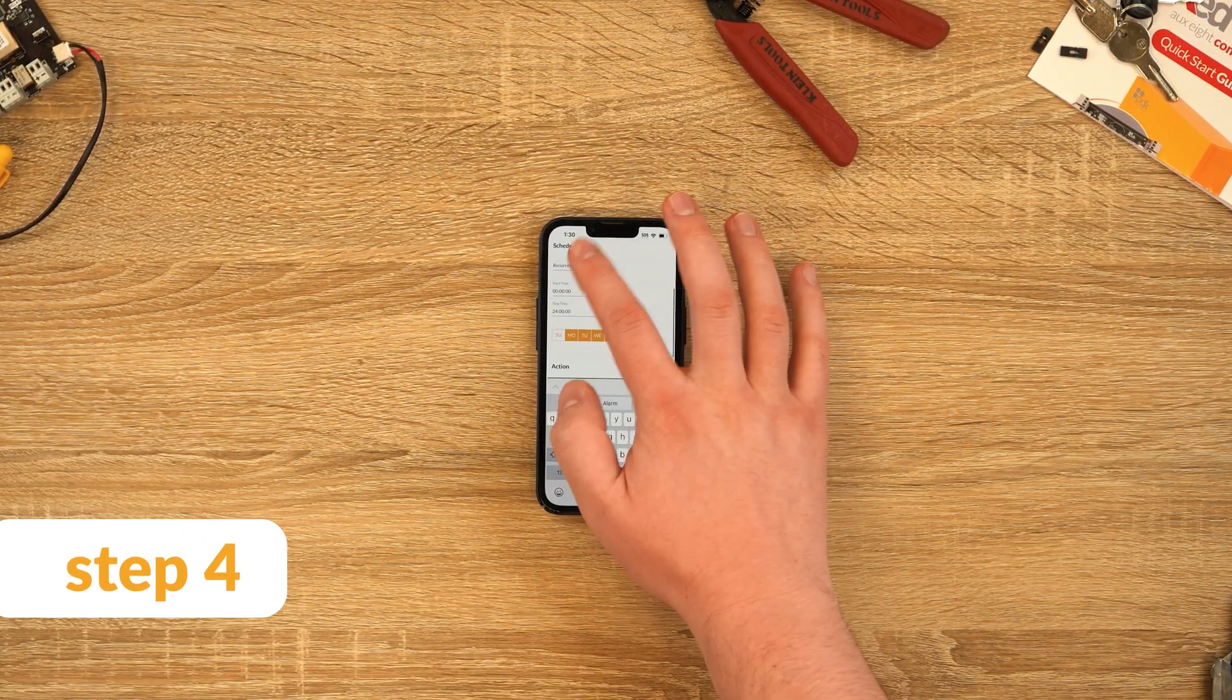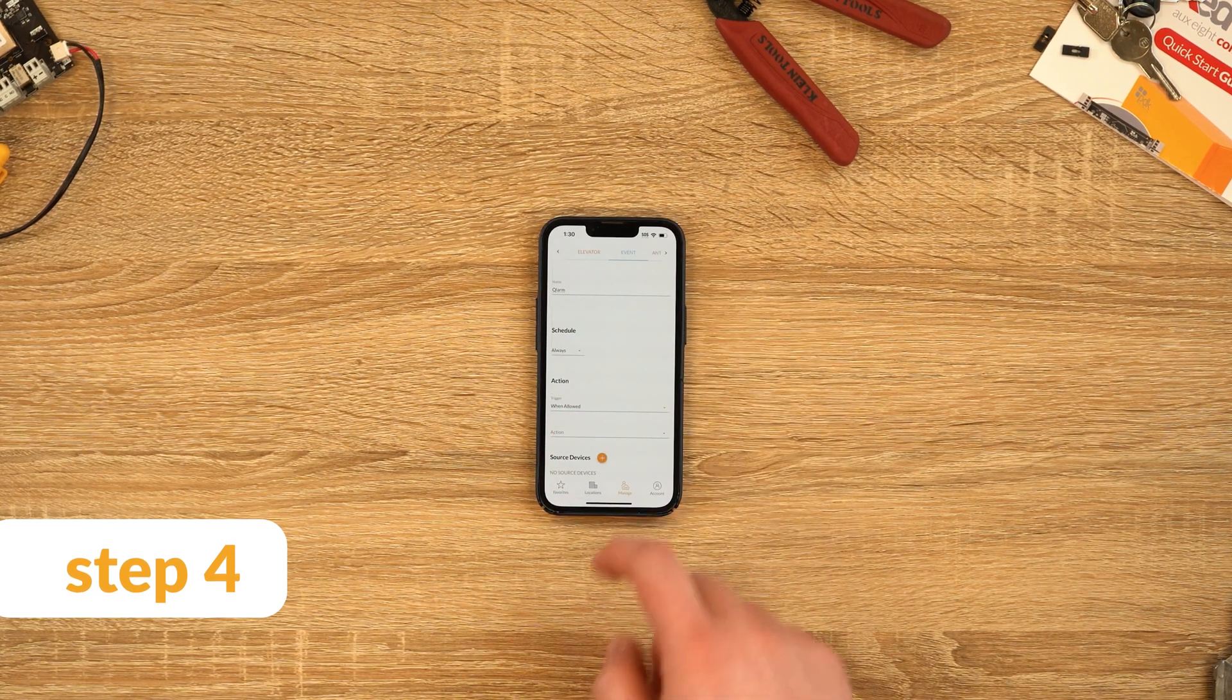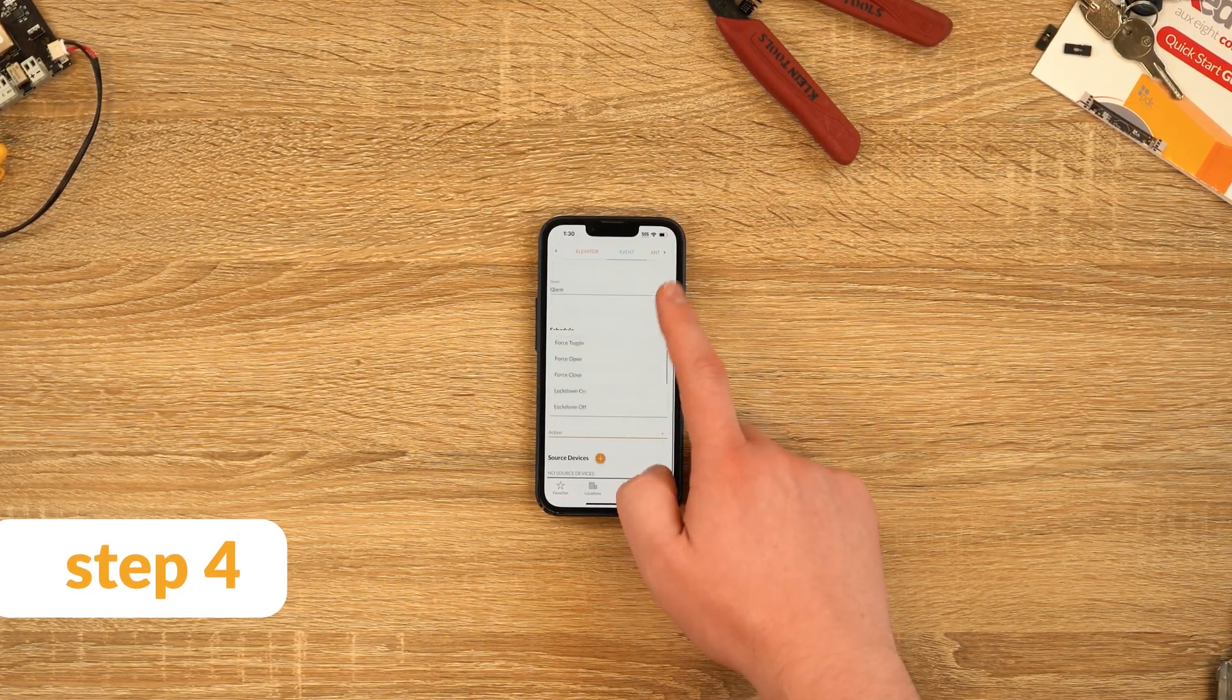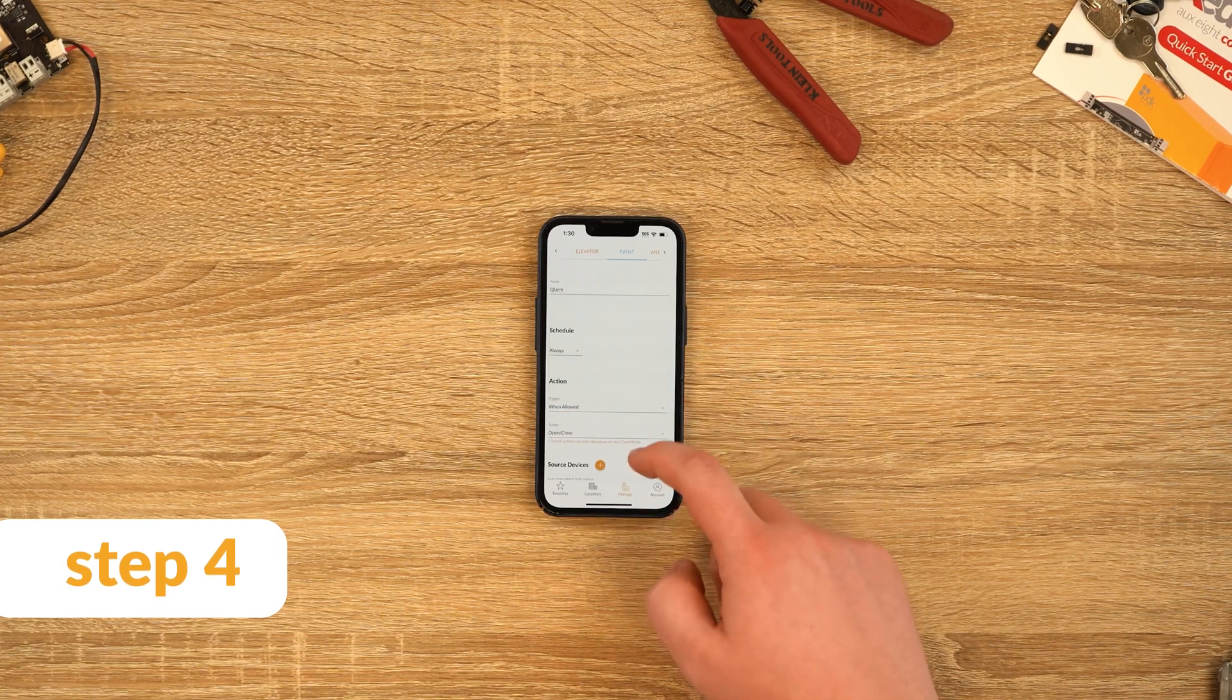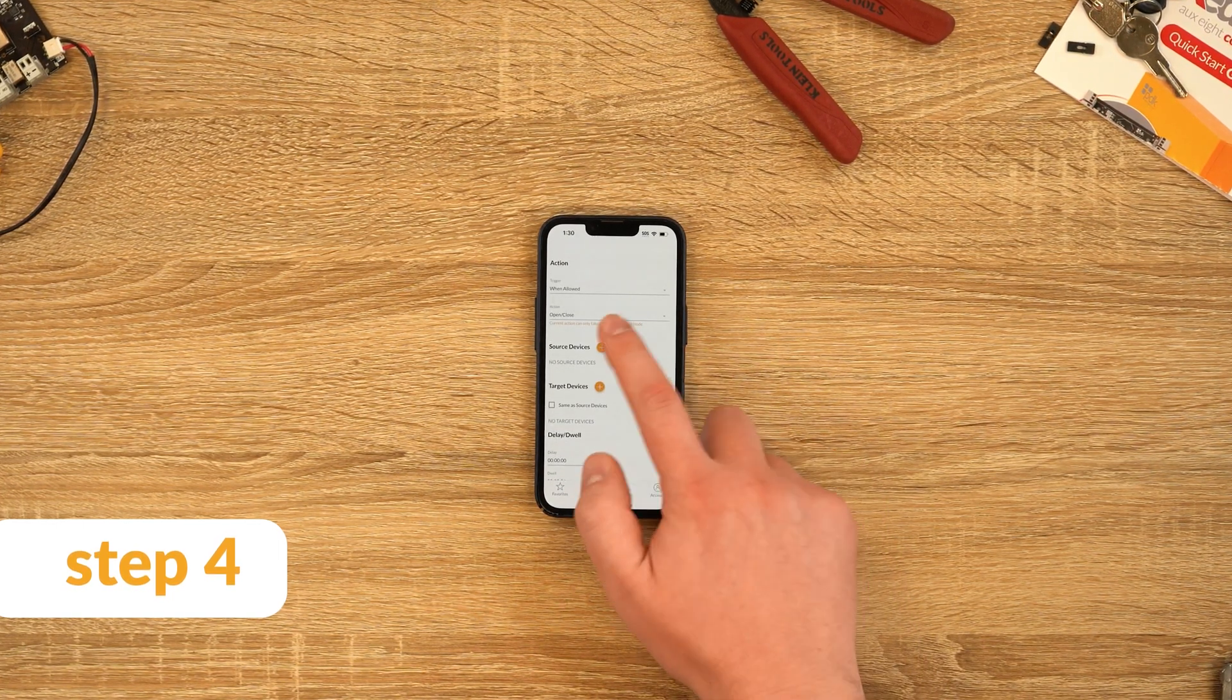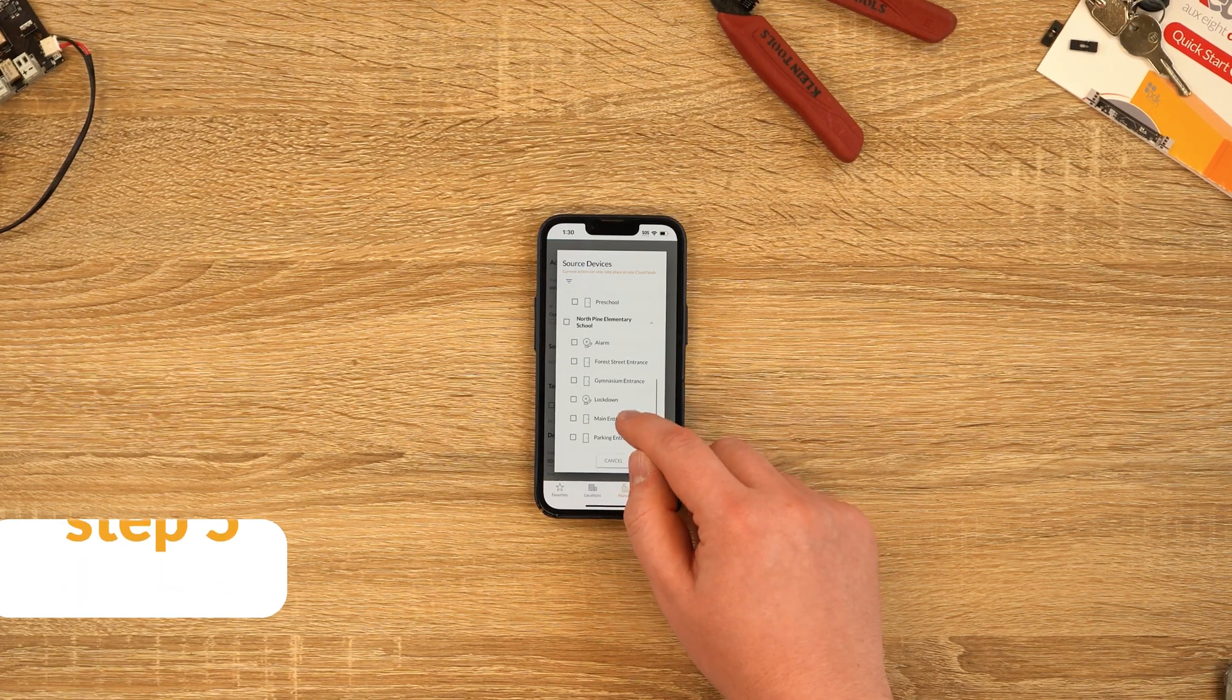Step 4: On this page, your trigger will be your if statement while the action will be your then statement. We want our statement to be if access is allowed then open and close the alarm panel relay. Therefore, we populate trigger with access allowed and action with open/close.